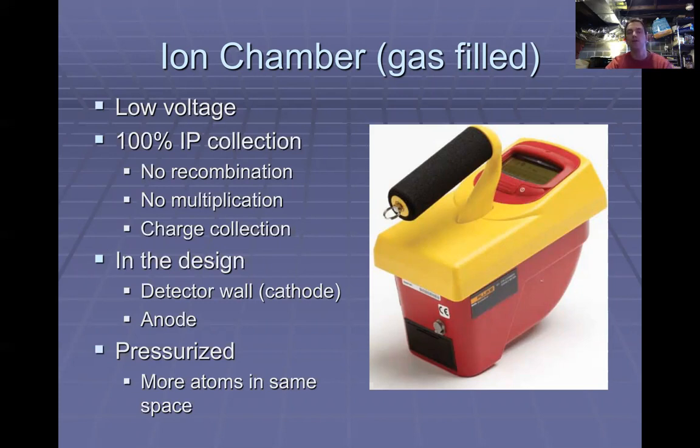It's a very, very faint charge, but then you have sensitive electronics inside of this meter that allow it to actually measure that charge, that voltage going across, and it can give you a dose rate. The more ionizing events that happen in that volume means there's more charge, and that means that there's more radiation present. So it will give you a higher reading.